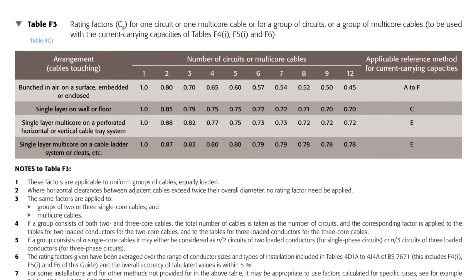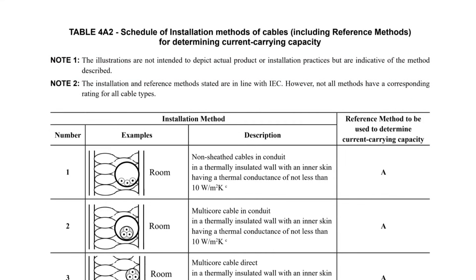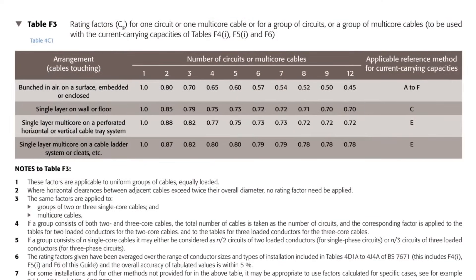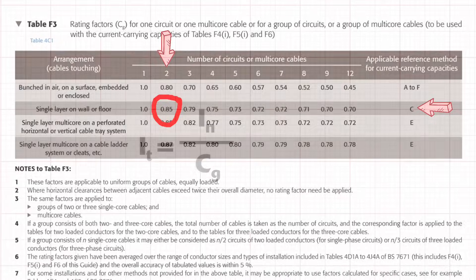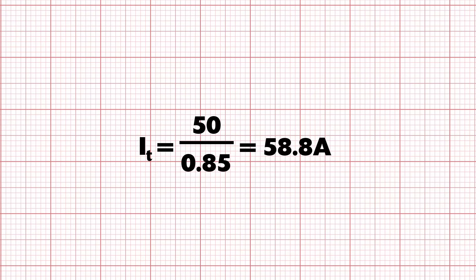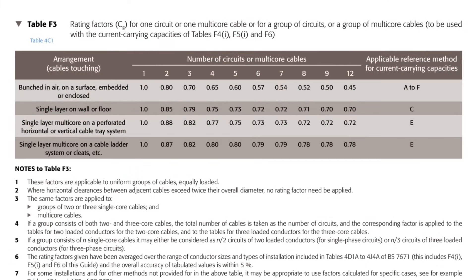If you're not sure which reference method to use, you can match the description from the left-hand column, and there's also helpful information in table 4A2 of BS7671. Let's assume we're working in a domestic installation, clipping the cable to a surface — that gives us reference method C. With another circuit alongside it, that's two circuits in total. Two circuits in a single layer on the wall gives a factor of 0.85. So 50 divided by 0.85 gives us 58.8 amps. Interestingly, if we bunched those cables together and clipped them to the surface, we'd use a factor of 0.80, meaning our cable would need to carry even more current.